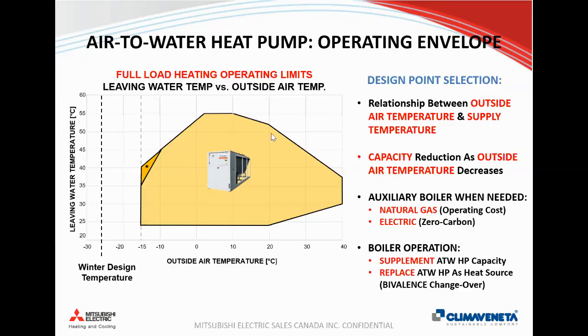So for example, if we look at a winter design temperature that's below -20, we're talking about using an air-to-water heat pump. We'll simply switch over to an auxiliary boiler whenever we need hot water supply below the cutout of the air-to-water heat pump. But again, for the boiler operation, there's two different ways you can run it. You can size the heat pump to run with the boiler. In those instances, you're still restricted by the limitations of the heat pump. So the heat pump can't provide any heat below -15.